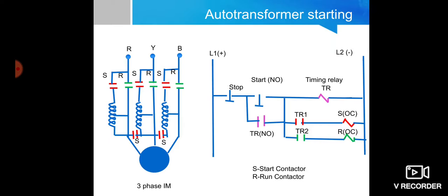TR normally open gets closed. So TR1 will eventually close, because of which SOC, that is your operating coil for the starting contactor, will get energized, and because of which all the contacts associated to SOC will get closed. What will be the direction of current? This will be the direction of current. This tapped voltage will appear across your stator. So like this, this is going to appear across the stator, whatever tapping you have taken. So a certain amount of voltage will appear.